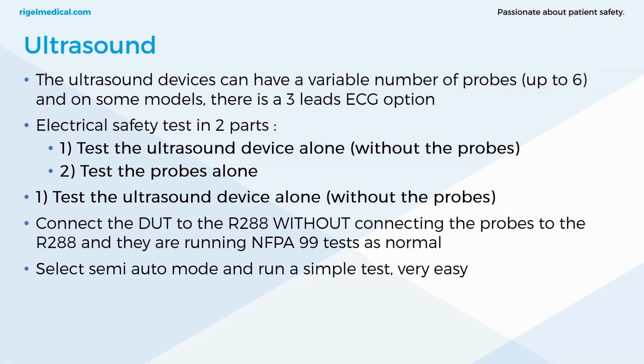A quick overview of ultrasound testing, because we do sometimes get queries on this. How do you perform it? Ultimately, you should contact the manufacturer to ask them about the process of testing their ultrasound probes. But there is guidance that we provide for testing ultrasound. We do it in two parts. So we test the ultrasound alone without the probes, and then we test the probes alone.